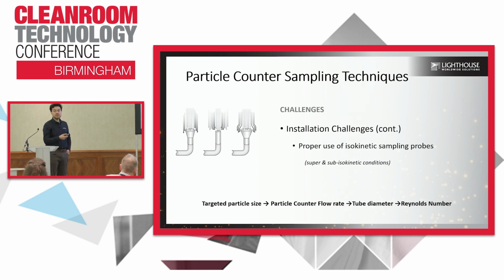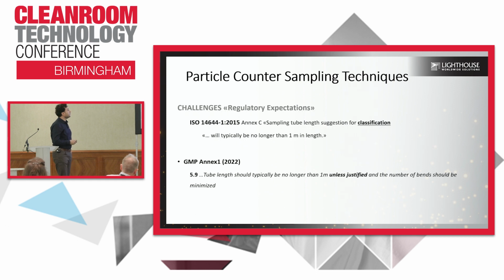If it is turbulent, it is fine, because in turbulent air, we don't really need to see a certain amount of air within the air column. But if it is unidirectional, under unidirectional conditions, we really want to focus on this area without generating any turbulence. These are the two expectations from the regulations.